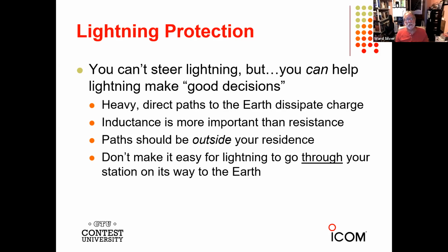For lightning protection circuits and conductors, inductance is more important than resistance. The voltage caused by a changing current is equal to the rate of change of the current times the inductance. Even straight wire has inductance. You can get, I think, 300 nanohenries per foot, and under a typical lightning surge, where you're talking about kiloamps per microsecond of change, you can get hundreds or thousands of volts just between one end of a straight piece of wire and the other. So you want to minimize inductance. It's not so much the resistance, it's inductance. So: straight, wide, low inductance paths.